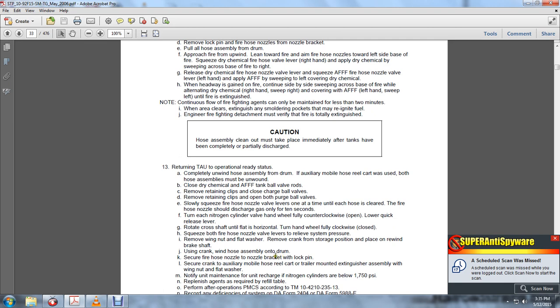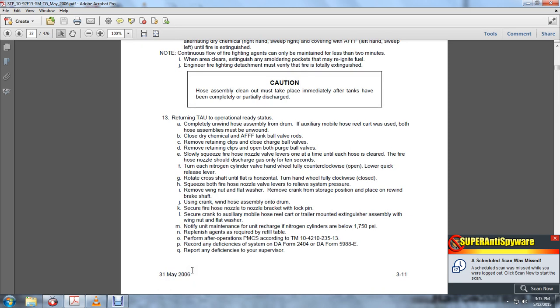Secure the crank. Auxiliary mobile hose reel cart, trailer mounted on the extinguisher assembly. Wing nut and flat washer. Notify maintenance of the unit. Recharge the nitrogen cylinders at 1,750 PSI. Replenish the agents required by the refill table.